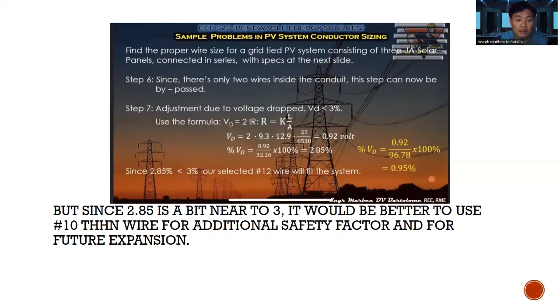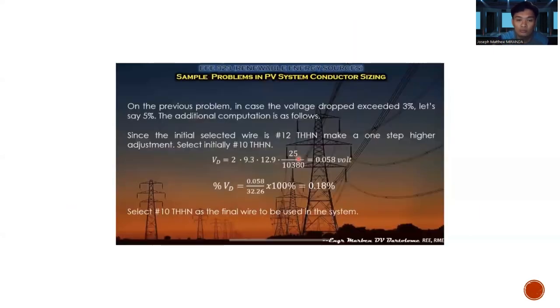But since 2.85 is a bit near to 3, it would be better to use number 10 THHN wire for additional safety factor and for future expansion. So, kunyari, may gagawin pa tayo doon sa bahay na yun, or mag-adjust tayo ng bahay natin, syempre, magdadagdag tayo ng wiring. So, number 10 THHN will fit the system for the future expansion.